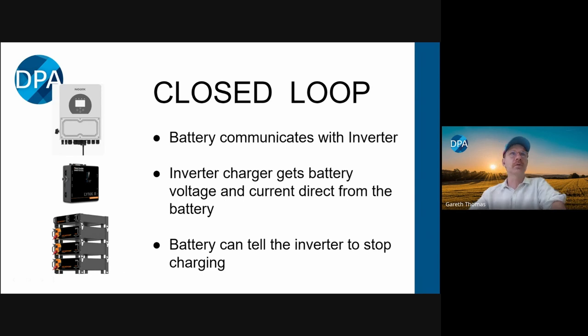That's pretty important, because when you're troubleshooting a system, it's important to see what the inverter thinks the voltage is versus what the battery thinks the voltage is. If those are drastically different, that might mean you've got a cabling problem. If the voltages are pretty much the same when there's no current, but then get wildly apart once you start putting current into the battery, that means you've got high resistance in the circuit. That's important for monitoring and seeing how the system performs.